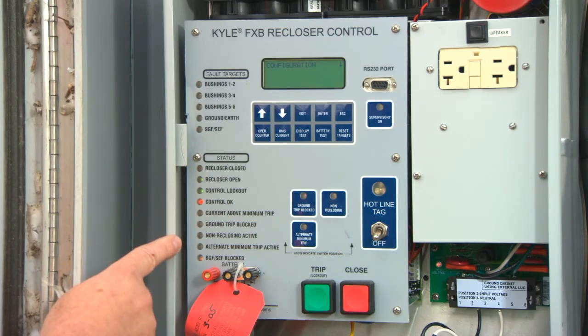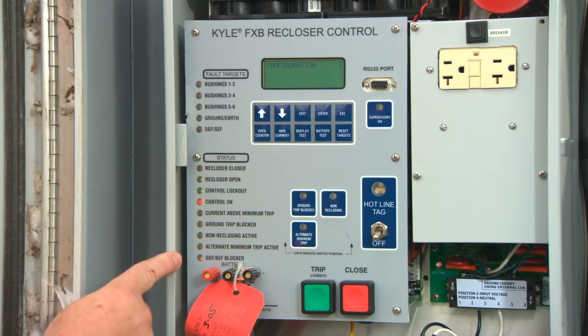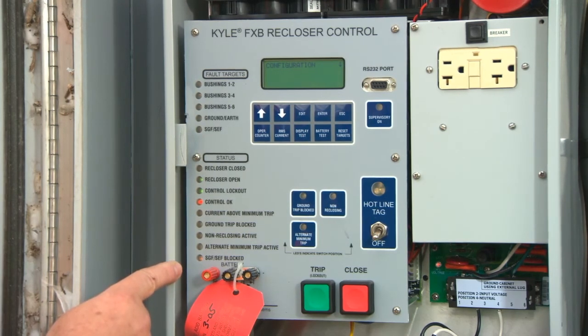Non-reclosing active will activate when you push the non-reclosing button or when you set a hotline tag, your hold-off feature. Alternate minimum trip. There are 3 settings groups available in this control. If you were to push the alternate minimum trip setting button, this LED would be illuminated. Finally, sensitive earth blocked or SGF-SEF is illuminated with an amber light. Since this is not activated in any of our controls, this light will remain off.